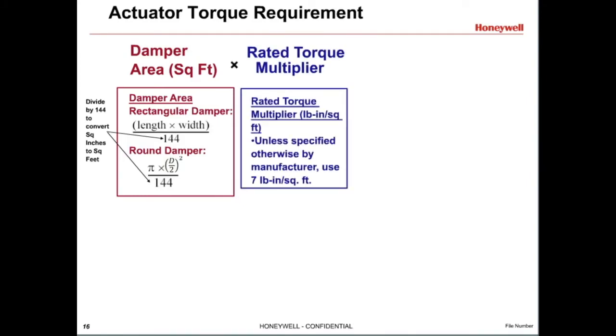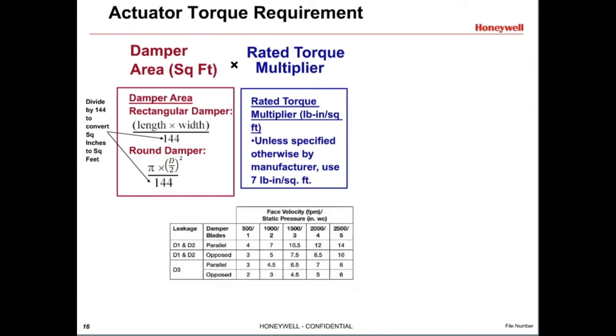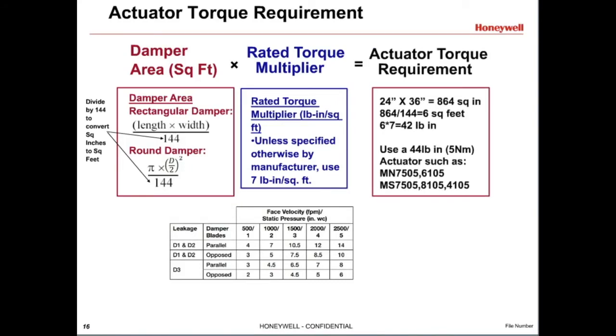Once the damper area in square feet is calculated, multiply this by the rated torque multiplier. Unless specified differently by the damper manufacturer, multiply the area in feet by 7 to determine how much torque is needed. For a 24 by 36 inch damper, multiply these dimensions together, then divide by 144 to get the damper area in square feet, 6 in this example. Then multiply that by the torque multiplier, we will use 7, to get the torque required to operate the damper. It is 42 inch-pounds in this example.